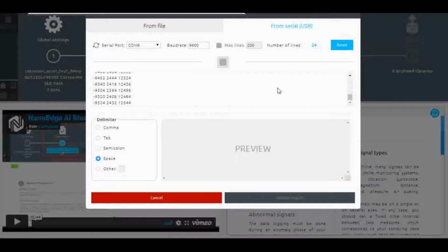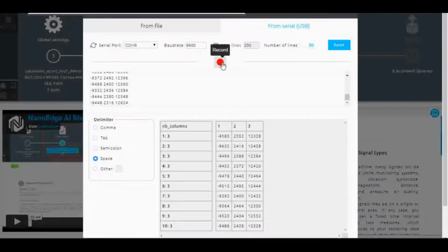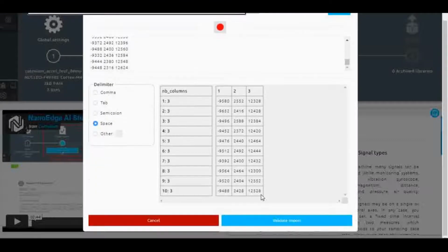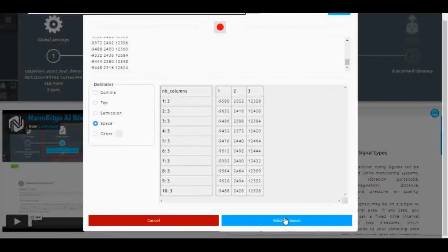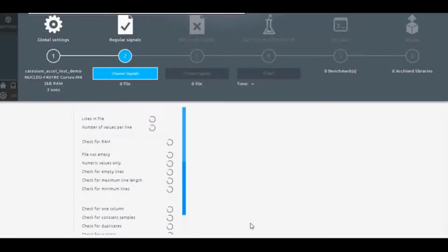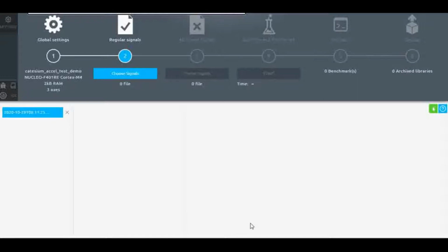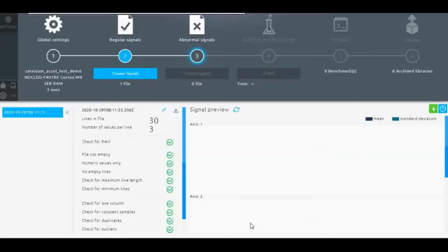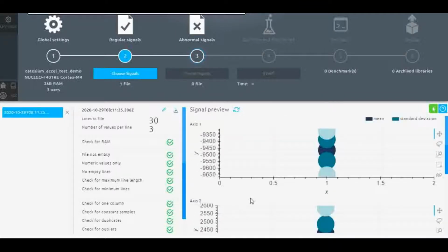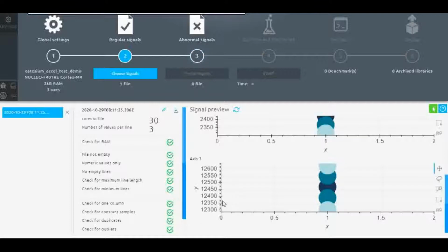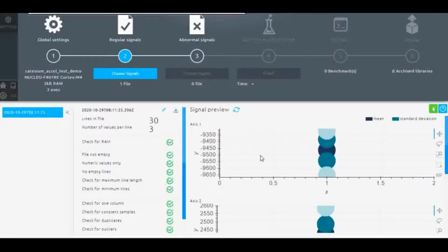and after that I will stop it from here, and as you can see, now it is like a regular signal, so I am not changing the sensor. I didn't lift or change the sensor. So now I validate the import, and now it is trying to see whether the data came properly. So yes, the data came properly here, and you can see the x-axis, y-axis, and z-axis, all 3 axes, the values are coming properly. It's like in this range.